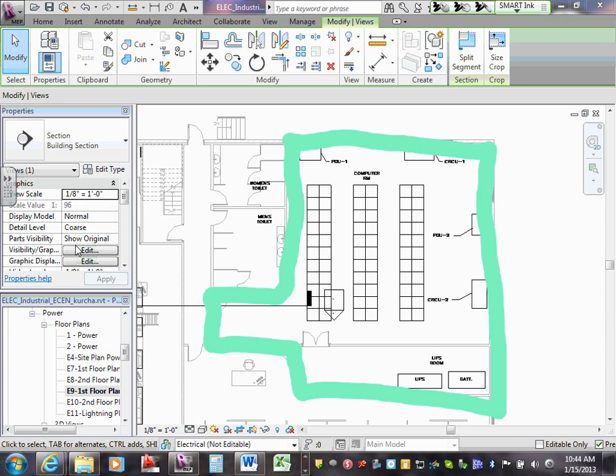And in this system here, you're going to use smoke detectors, but what typically people are using now is Vesda. It's just an air sampling system. So you're going to have one panel in this area. You probably have two panels. They have a 4-pipe system that you're going to want to look at 4 zones. And you put one panel here. What you got to do is you got to cross zone them as well.